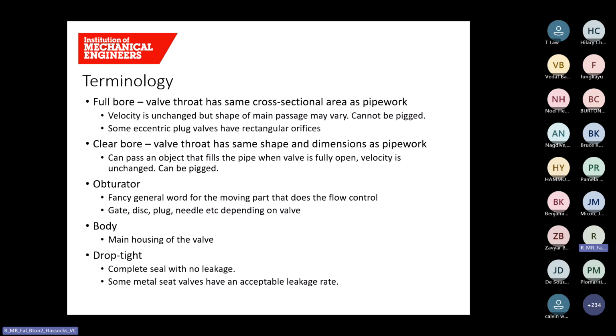Before we discuss individual valve types, I'm going to run through some terminology that's used for valves. First off, full bore. This is to do with the valve throat, which has the same cross-sectional area as the pipework. So that means that when the flow passes through the valve, the velocity is unchanged, but the shape can vary. This type of valve can't be pigged or cleaned. Some eccentric plug valves, for example, rather than having a circular opening, they have a rectangular shape.